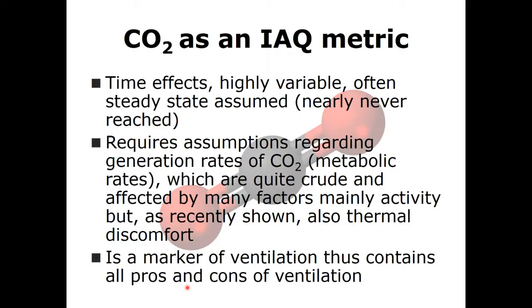So if we use CO2 as an IAQ metric, actually CO2 is a metric of the ventilation, because it provides us with information about how much outdoor air is coming indoors in the spaces that are occupied by people. So basically, it should be put together in the same group as the ventilation. That's the index of IAQ, and it can only be used when there are people in the space.